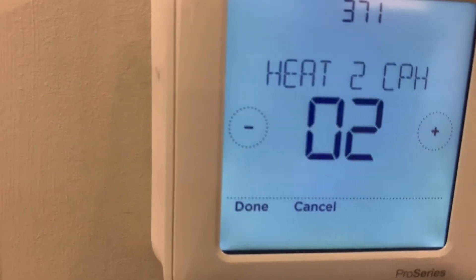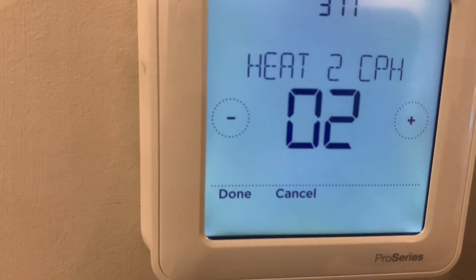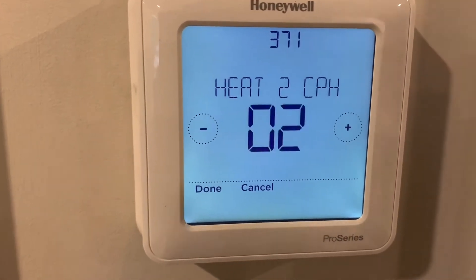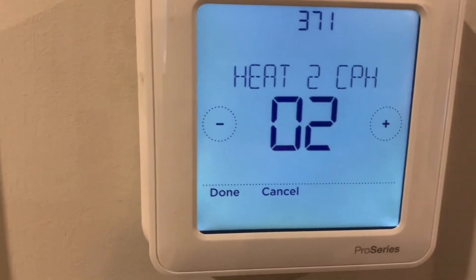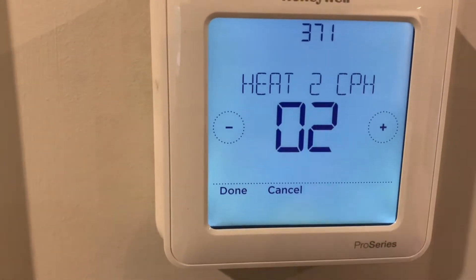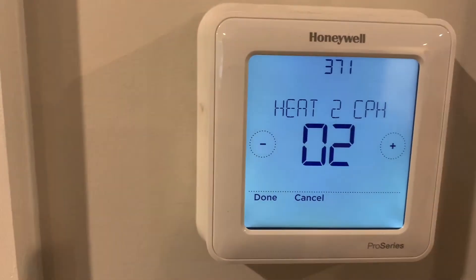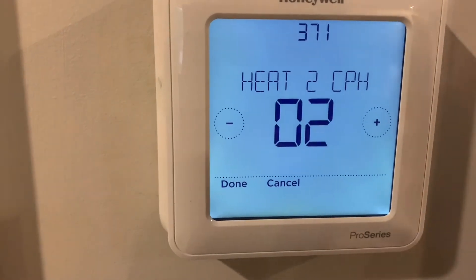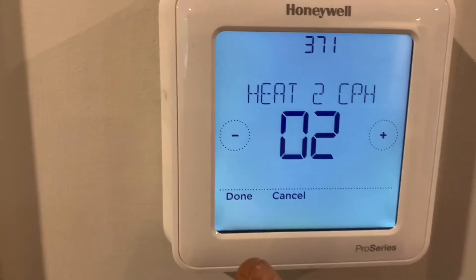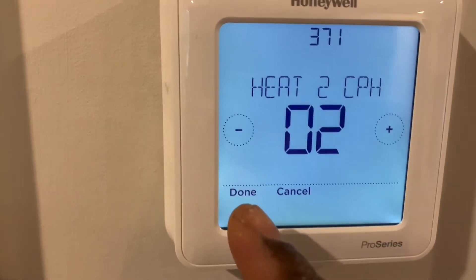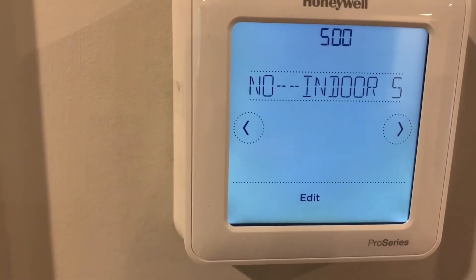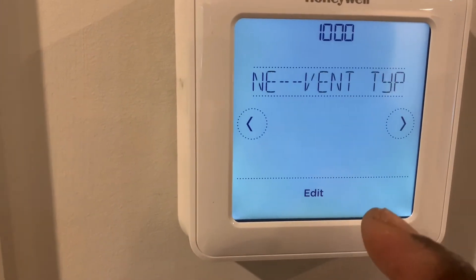If it does turn on, it will cycle very little, because that would mean the boiler is not working and we've gone past the 10-minute delay with the temperature not going up. This is a worst-case scenario — I only want to use the heat pump or compressor for heating if the boiler is the primary and it's failed. It's a unique setup but it works. No indoor sensor, no vent type.